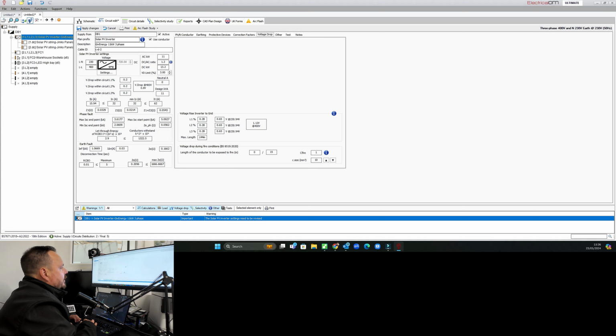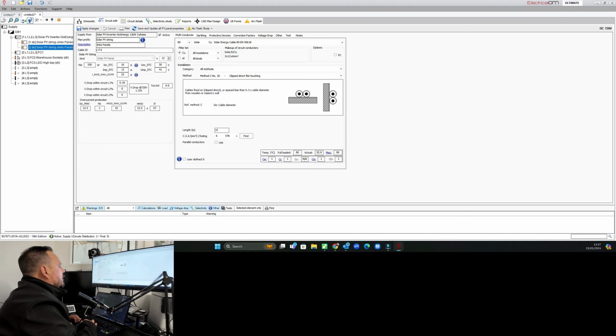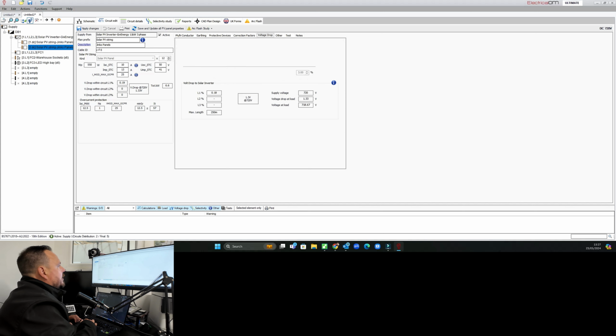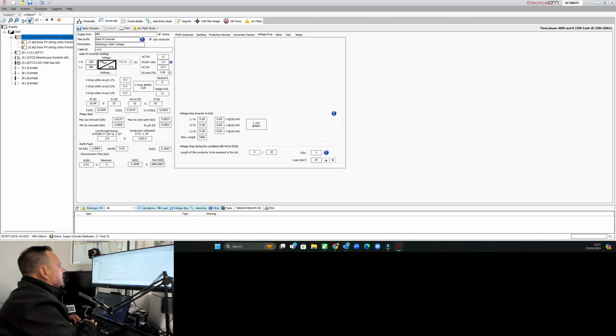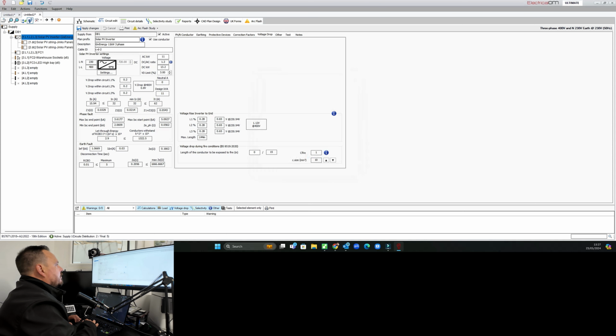So this is on the actual inverter, and it's giving us a maximum cable length, and that's trying to stay within 2%. I think I've got that set to on this particular thing. So if we save that now, we can see our problems have all cleared away. So the volt drop's all much happier. It's dropped away because we've changed the inverter sizing basically, which is what we did in this settings box here. As soon as you've got that set up to match with what's connected to the system, you start to get that generating across all three phases. So we can see that now taking place, which is smashing.